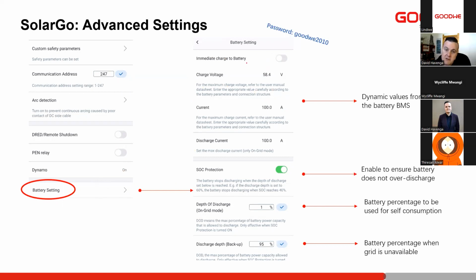So immediately charge the battery. So if you are on site and your batteries are very flat and you're expecting a power outage or anything like that, you can use this function to immediately start to charge the battery from the utility. Same if you're doing a new installation and maybe it's going to stand for a while, just charge the batteries up to their full before you shut the system off.